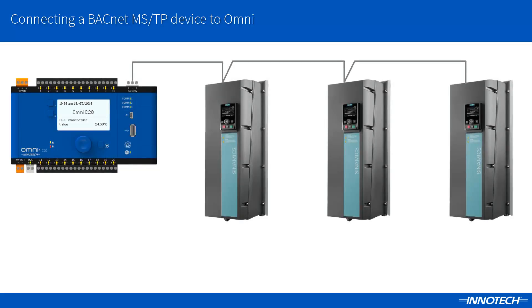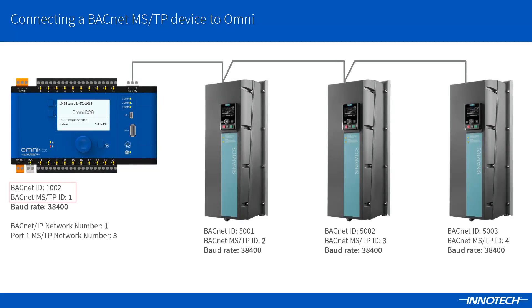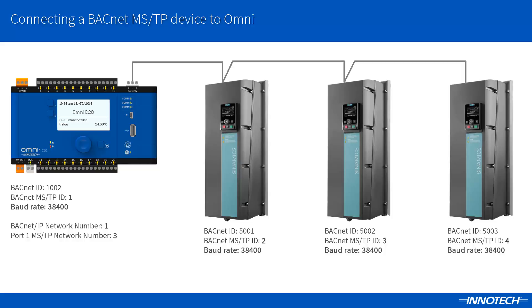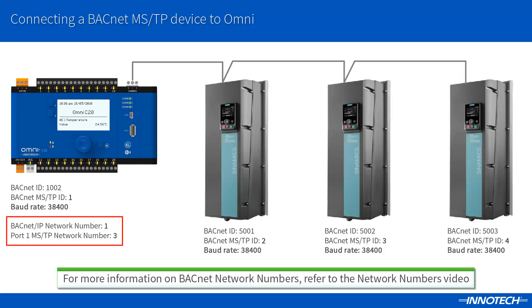In addition to the Omni controller, each MSTP device needs to have a unique BACnet MSTP instance. This is in addition to the BACnet instance as shown. In this example, all devices are configured correctly including baud rates and BACnet MSTP addressing. The configured Omni comm port needs to be set to a unique network number for the BACnet network. For more information on network numbers, refer to the relevant video available on the Innotech website.